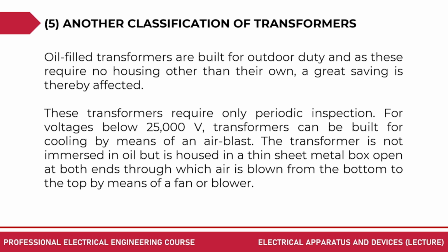For voltages below 25,000 volts, transformers can be built for cooling by means of an air blast. The transformer is not immersed in oil but is housed in a thin sheet metal box open at both ends through which air is blown from bottom to the top by means of a fan or blower. So usually these can be classified as the dry type.